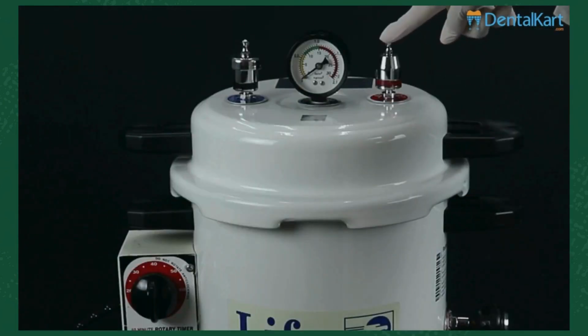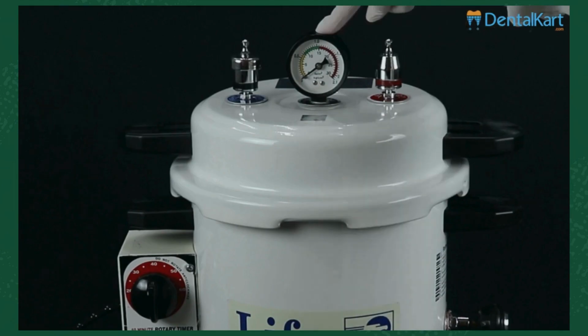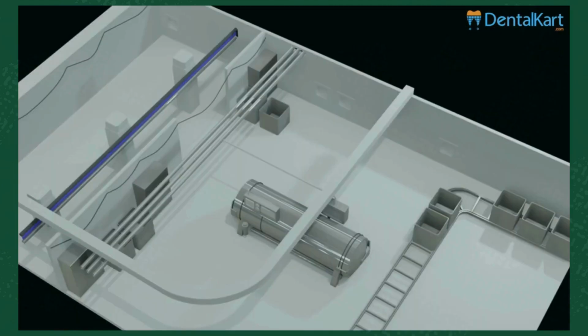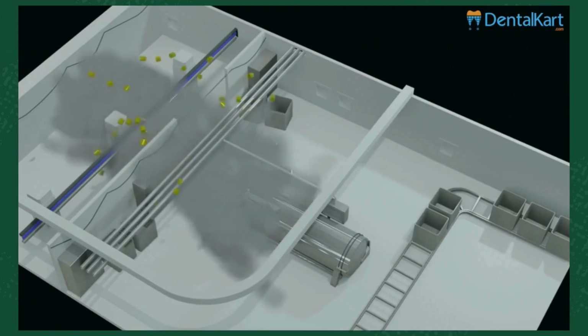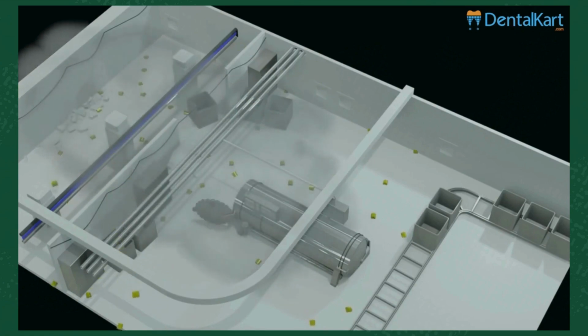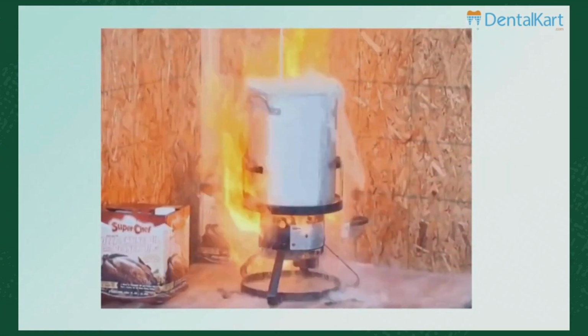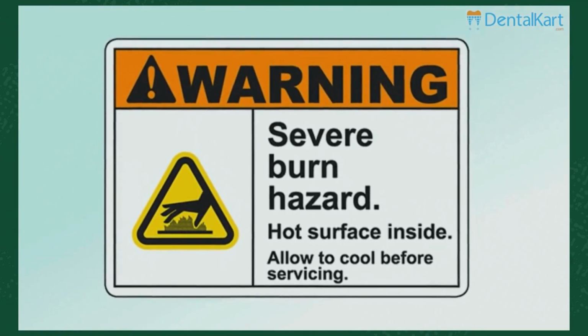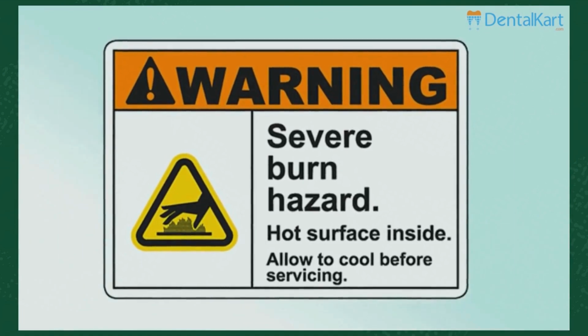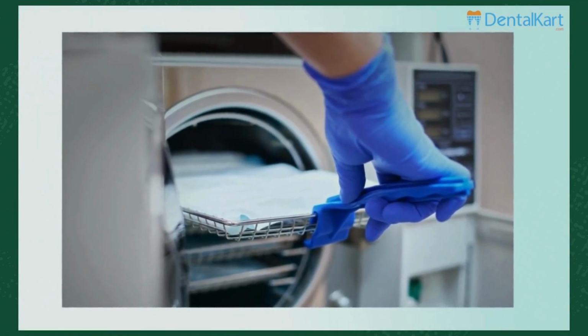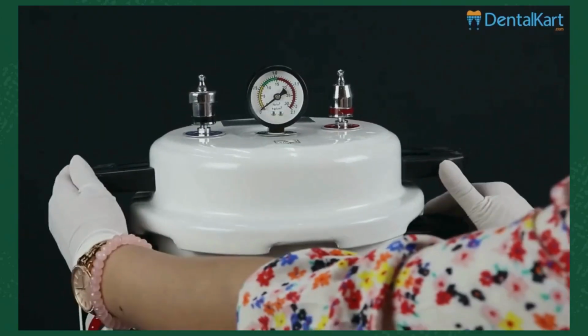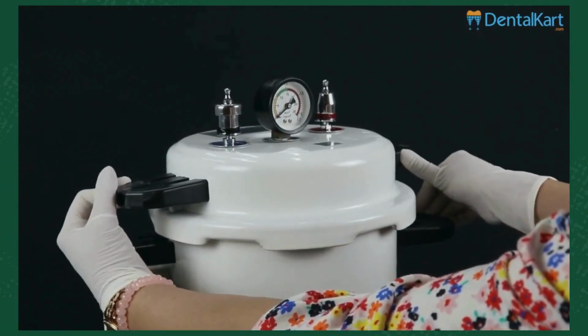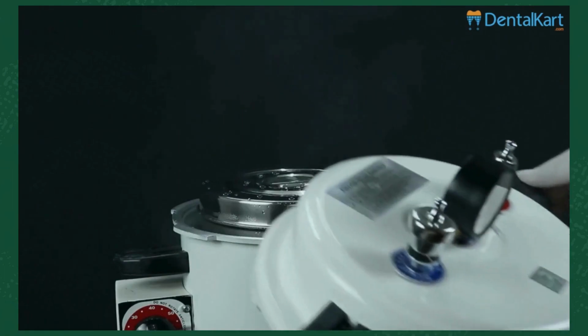Ensure the pressure regulating device is working fine to stabilize the pressure inside and also monitor the pressure gauge. The pressure and the heat inside the chamber might rise and escape rapidly if not balanced, causing an explosion which could prove fatal. A few other hazards are burn hazards. Be cautious of hot surfaces when loading and unloading the autoclave. Recently autoclaved contents inside will be extremely hot. Make sure to keep your face, body, and hands away from the escaping heat and steam when opening the lid of an autoclave.